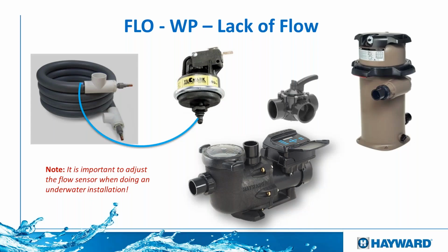Okay, so flow. The problem here with flow is going to be related to a pump. Maybe it doesn't have enough prime. Maybe the pump is not on. Maybe the motor is not working, or a dirty filter, or a valve in the wrong position, or maybe a bypass that is completely open. And last will probably be our flow sensor. These flow sensors are really good sensors, so the possibilities of them failing are not that great. So I will definitely look outside of the box before we replace a sensor.